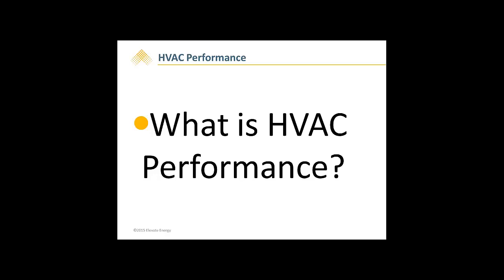Unfortunately, a furnace, heat pump, or air conditioner is not simply plugged into the wall and you're done. There's a lengthy installation process guided by a 60 to 70-page manual and performed by a seasoned, certified, and sometimes licensed professional. To assume all those professionals perform at the same level of work and that it's always perfect is not borne out in our field data. Rather, HVAC performance considers the impact the contractor has on the installation, commissioning, recommissioning, and sizing and selection. These processes are particularly impactful in a more difficult replacement environment.